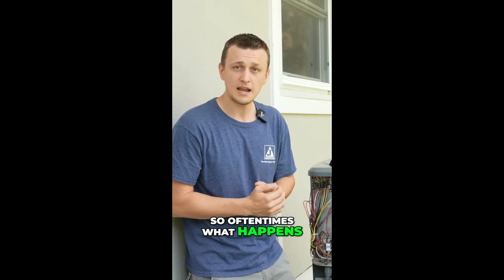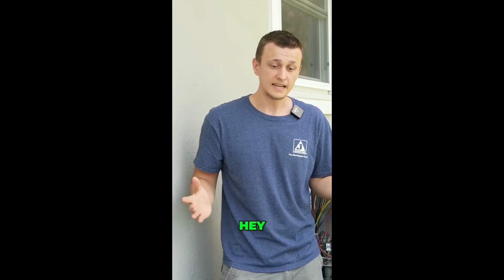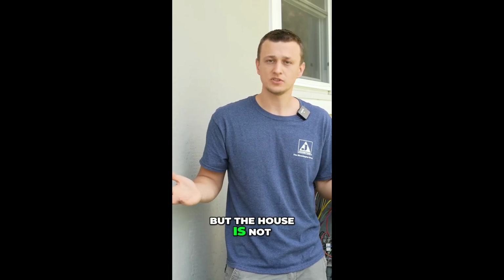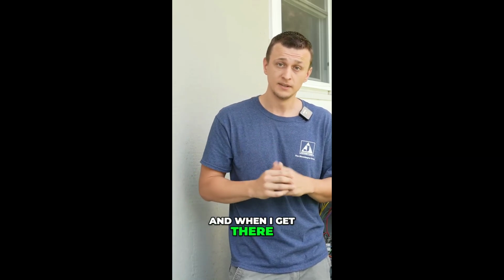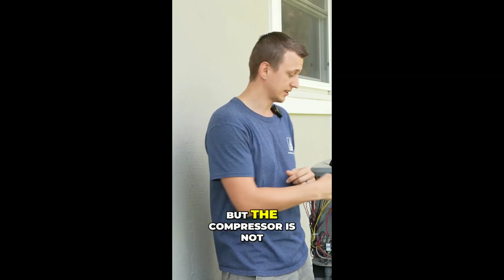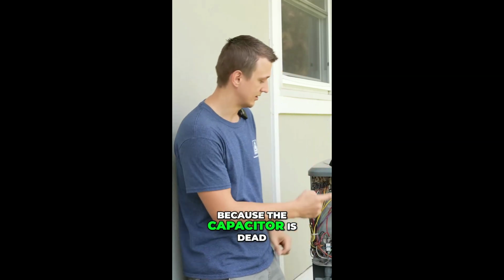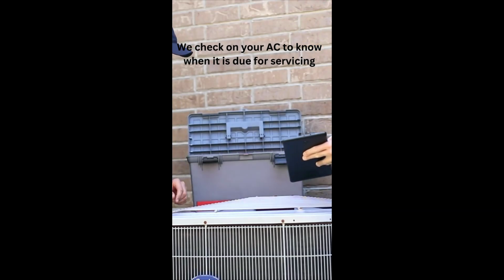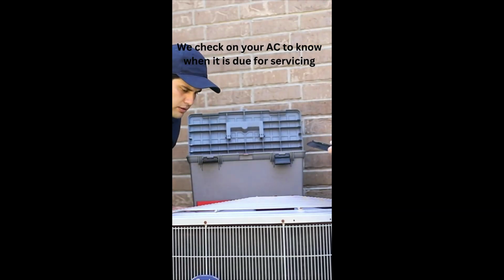So oftentimes what happens is a customer will tell me, hey, everything is working great, but the house is not getting cooled off. And when I get there, yeah, the two fans are working, but the compressor is not because the capacitor is dead. This is the reason why General Home Service Pro will check on your AC to know if it is due for servicing.